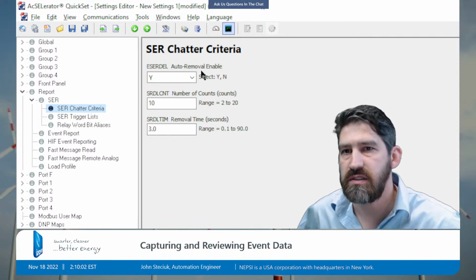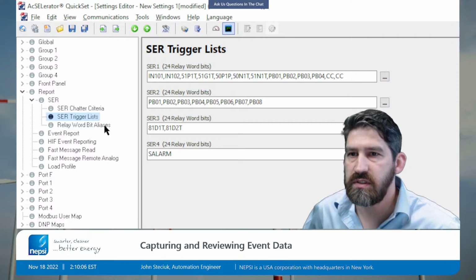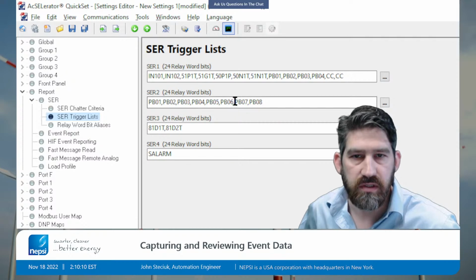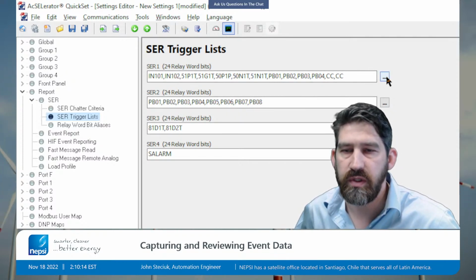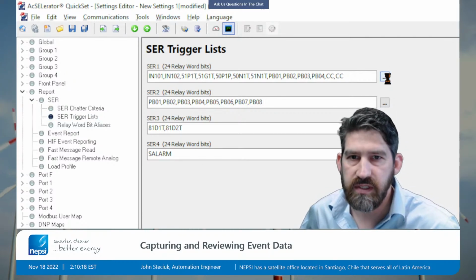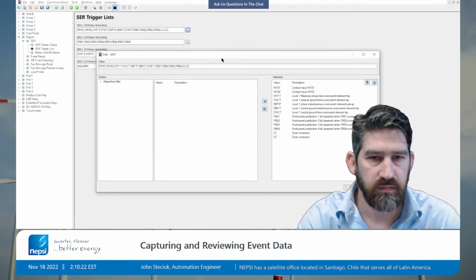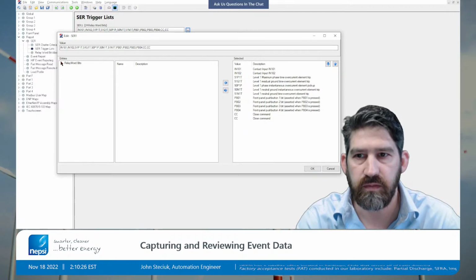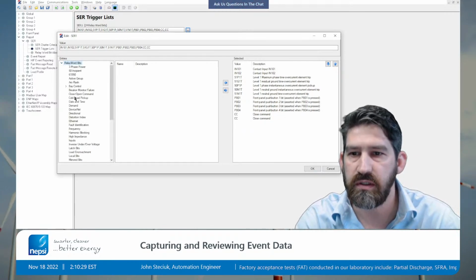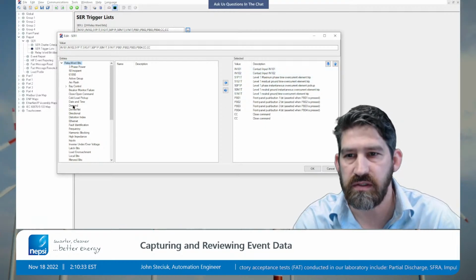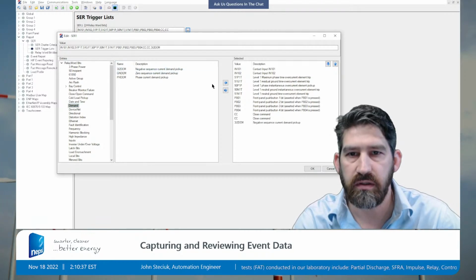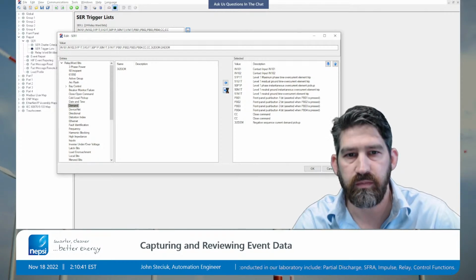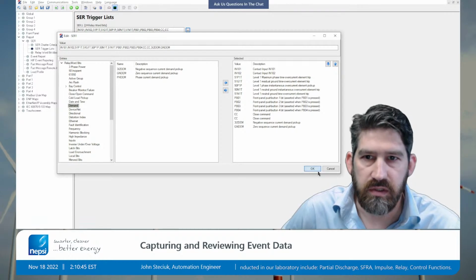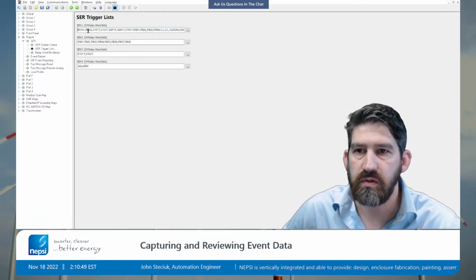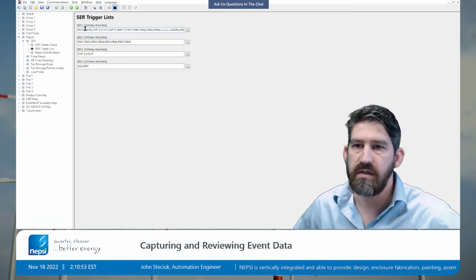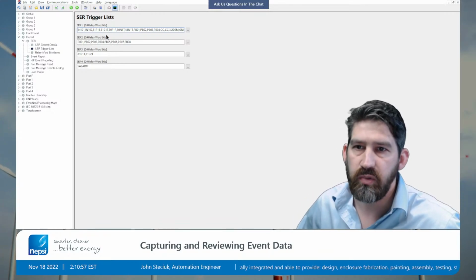The first setting in here is chatter criteria. We have trigger lists and relay word bit aliases. I'm going to start out with trigger lists because this is where you define which points you want to record the status of. So it's pretty simple. You select from this drop-down menu the data points that you want, and it shows what you selected over here, so you can either double-click or highlight a group and push the arrow to bring it over. Once you click OK, all of your points are shown in the SER. There are 4 different SERs available, and you can put up to 24 relay word bits per SER.